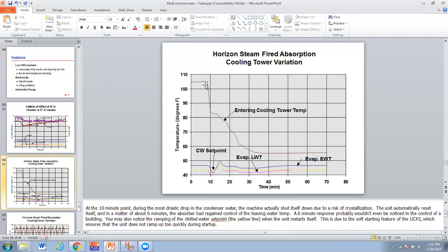Well, they didn't get all the way down to 55. I guess eventually we got down to 55 about here. But anyway, this is a big drop, and the machine goes, whoa, Nelly, and shuts itself down. The unit automatically reset itself, and in a matter of about 6 minutes, the absorber regained control of leaving water temperature. So here's our leaving water temperature.